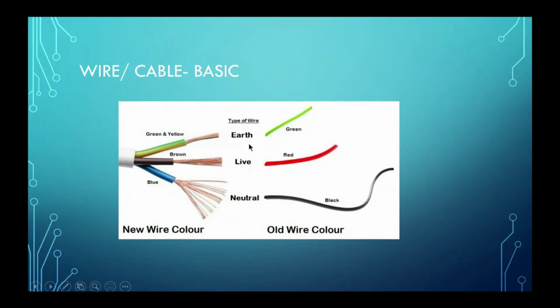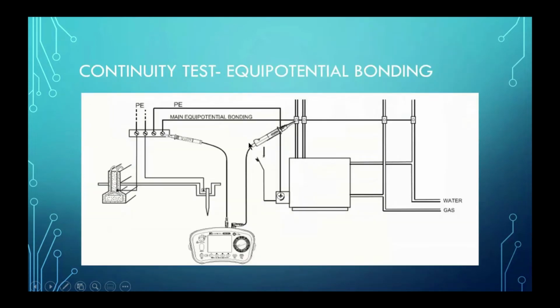So we proceed further. One of the functions of our instrument is to do the continuity test. This diagram shows equal potential bonding. You can see my cursor here. Equal potential bonding means equal voltage bonding. All of these wires are connected to the earth electrode. The earth is normally 0 volt, so all these wires are 0 volt.